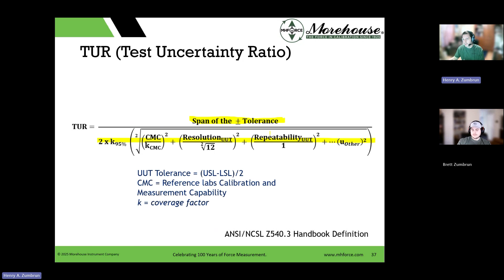So it depends on those two. The uncertainty you're only going to drive down so low. Like NIST can drive their uncertainty down to 0.001. If we're at 0.002 and they're at 0.001, they're twice as good as us. So if we say our TUR is 20-to-1, this would be 40-to-1 on that same instrument. So yeah, good question. You can keep driving it down.